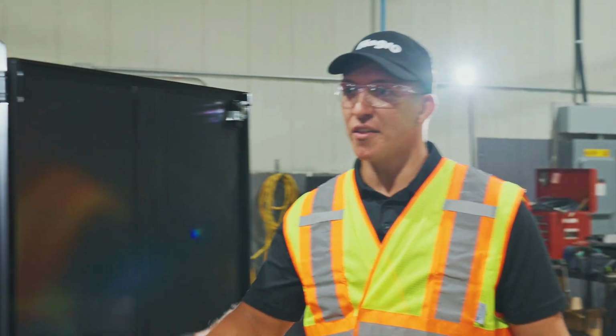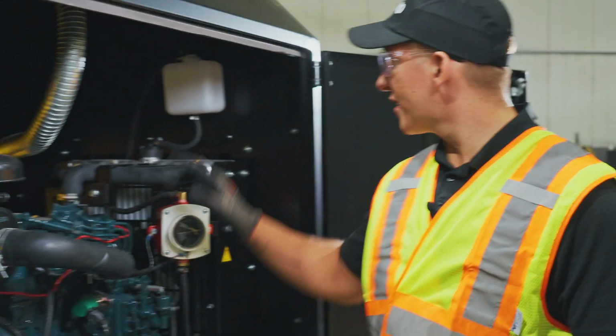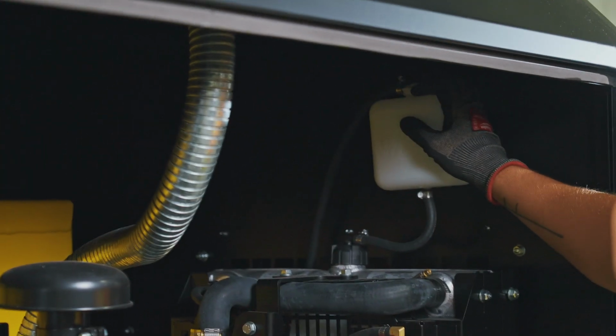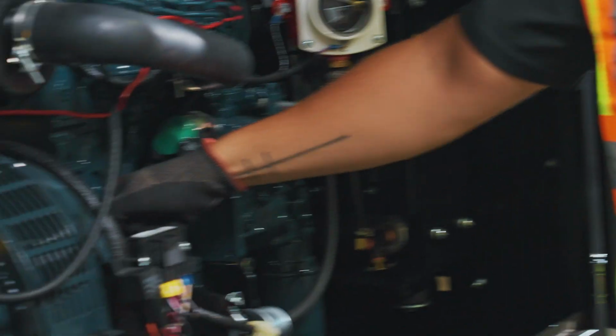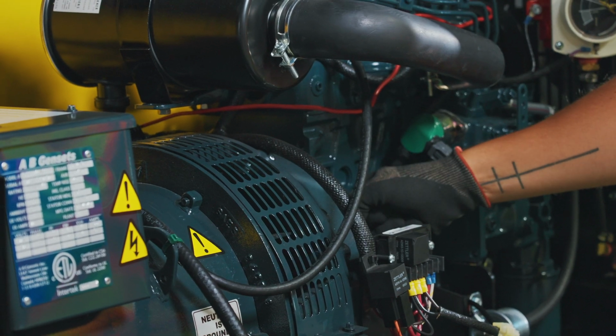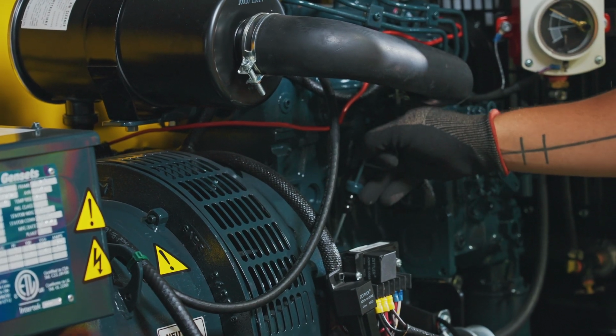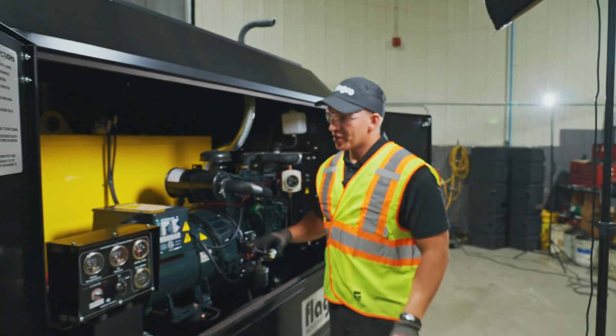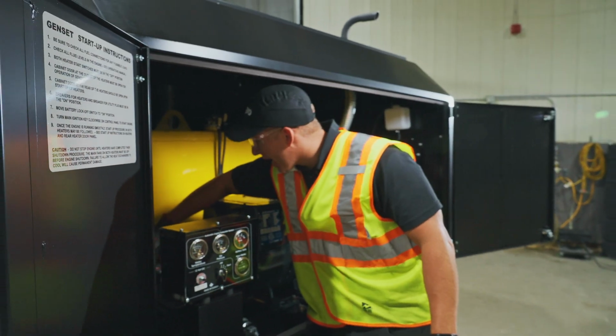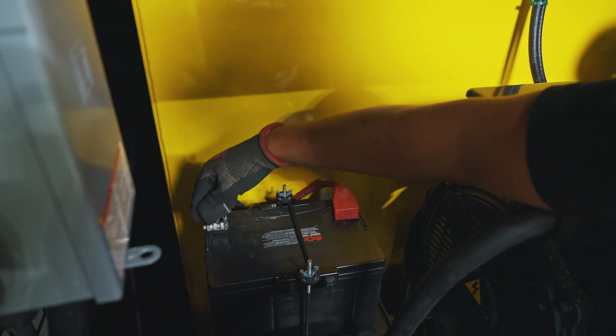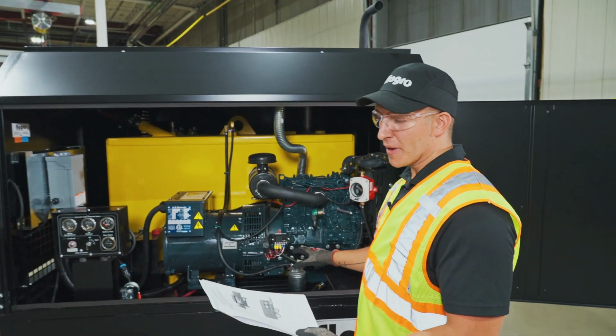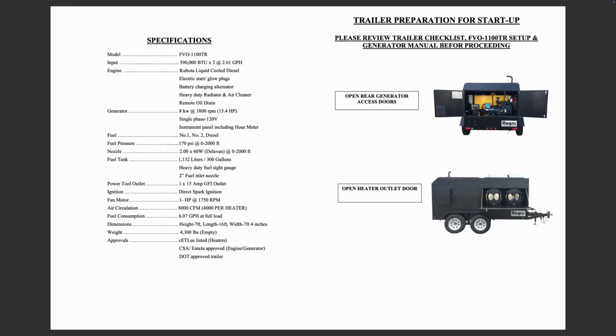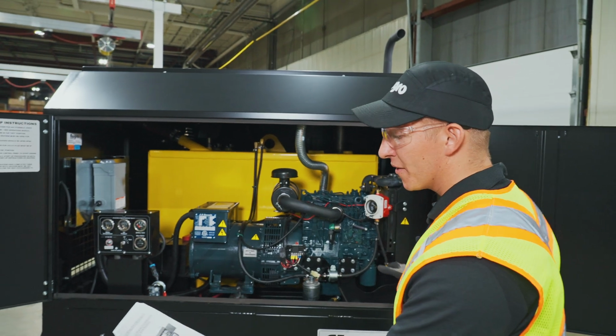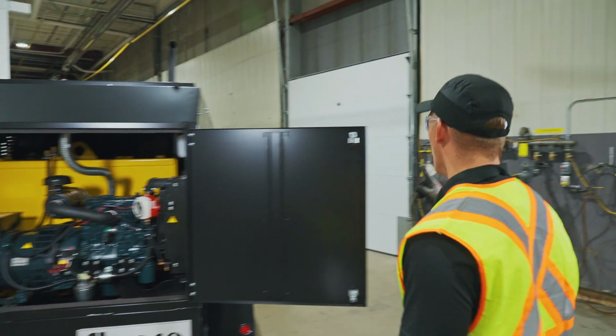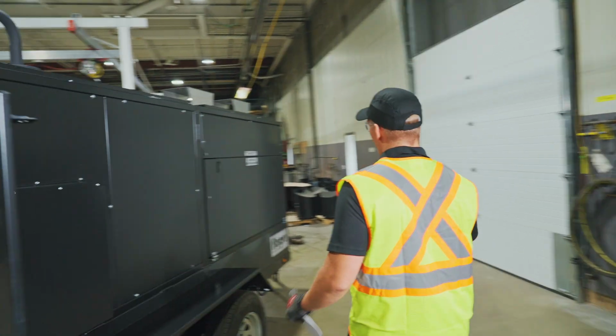All right, so moving into the backside, you're going to want to check your coolant levels on your genset. Be able to access here your oil levels. Pulling that dipstick out, make sure you have adequate oil. You want to check your battery connections in the back here, make sure they're snug. So if everything back here meets specifications, you can move into your preparation for startup. You want to have the rear genset doors open here and move around to open your outlet door.